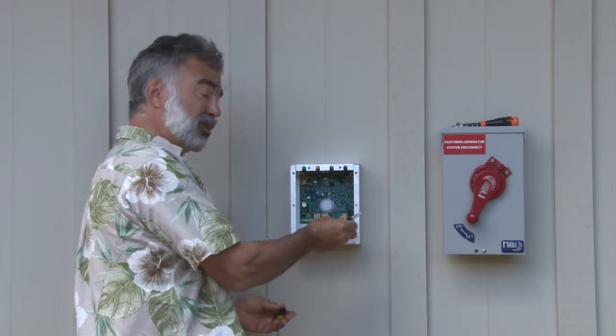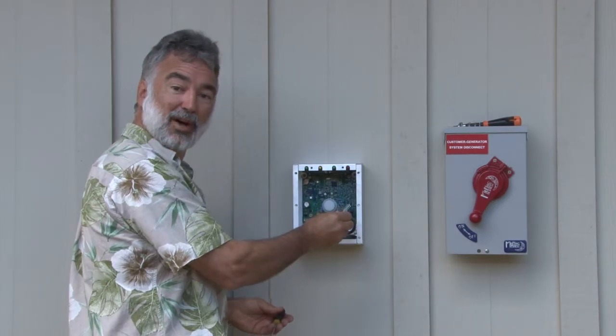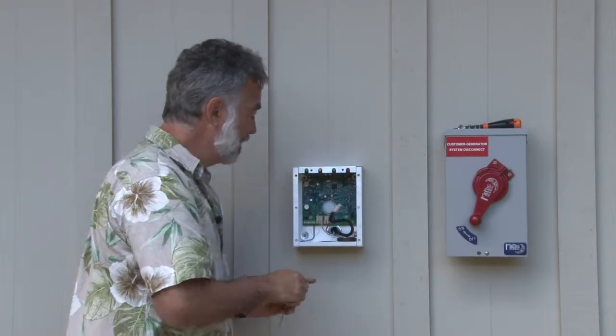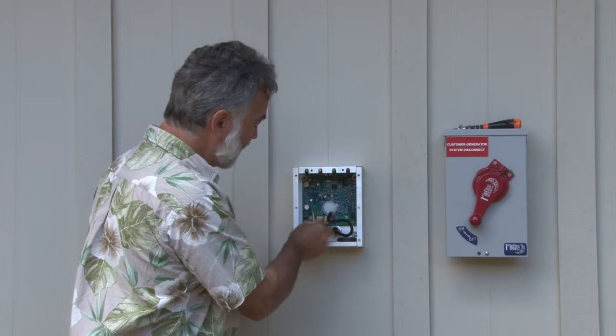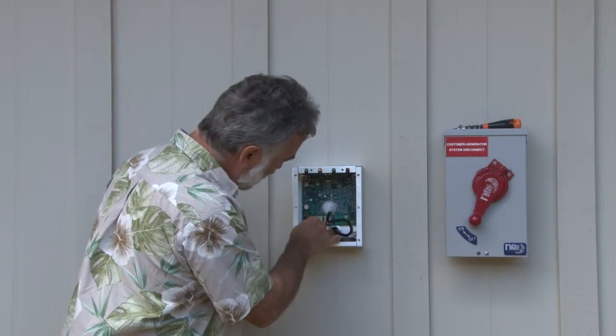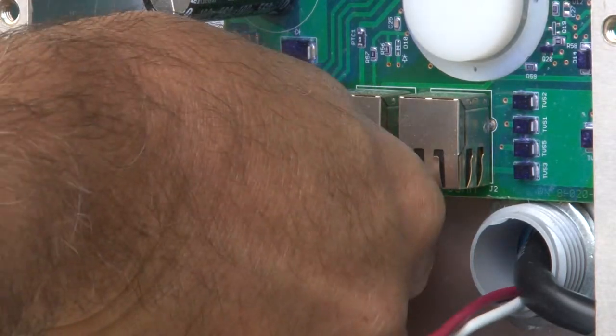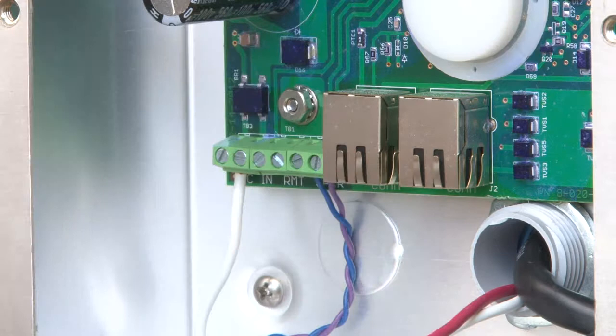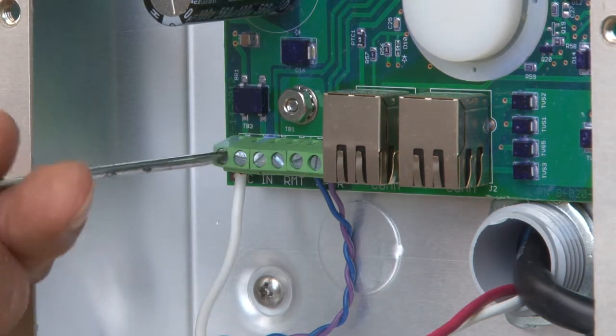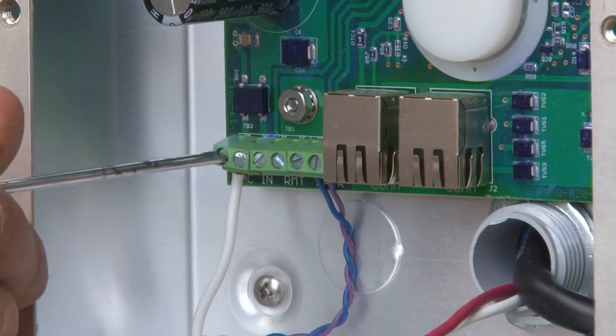The breaker is open because the combiner box isn't actually plugged into it right now. What we're going to do first is connect the power supply leads from the AC power supply over here to this terminal on the far left-hand side. This provides power during the night when the PV array is not active.